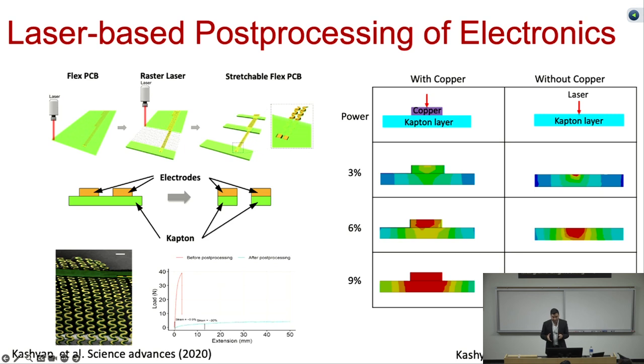And the way that really works nicely is that there's this sort of auto alignment or masking that happens. It's the copper material itself, the electrode traces, that when the laser passes over it, acts as a heat sink. So it protects the kapton layer beneath those traces, and then the rest of the kapton gets obliterated away. If you got rid of all of the kapton altogether, the copper would be too brittle and would just break itself. So this allows us to find a happy medium where it has enough stability that you can utilize it, but gets rid of enough kapton that it still ends up being a stretchable material.